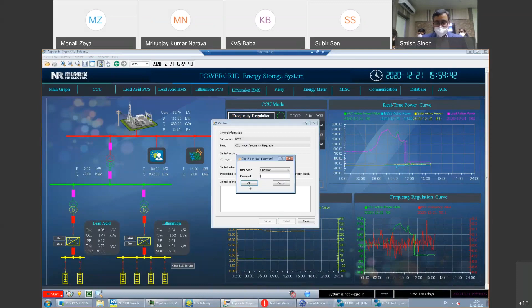Okay, so let us move ahead to this frequency regulation module. Can enable it first. So in the frequency regulation module, we have designed it with specific bands. So for example, 49.95 to 50.05 is one band. 49.75 and 50.25 is another band. And say 49.5 and 50.5 is the third band.